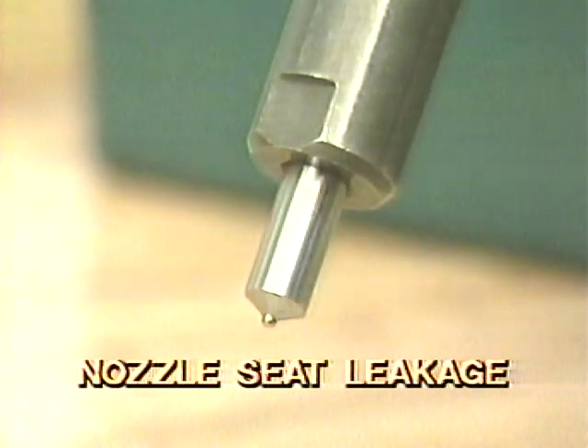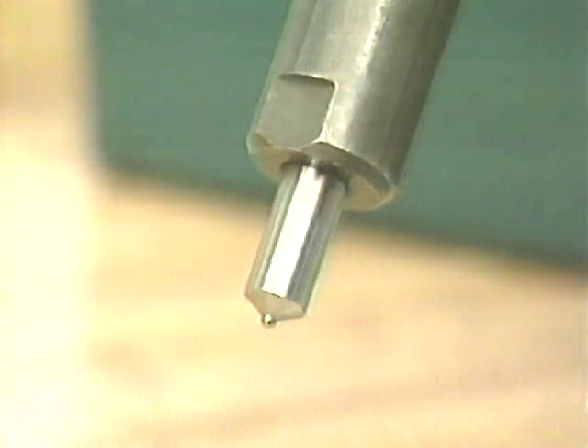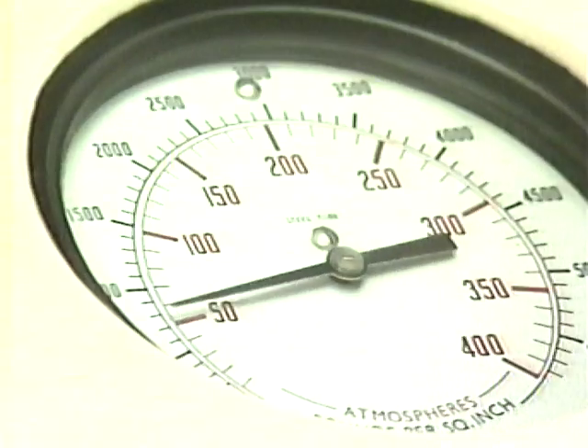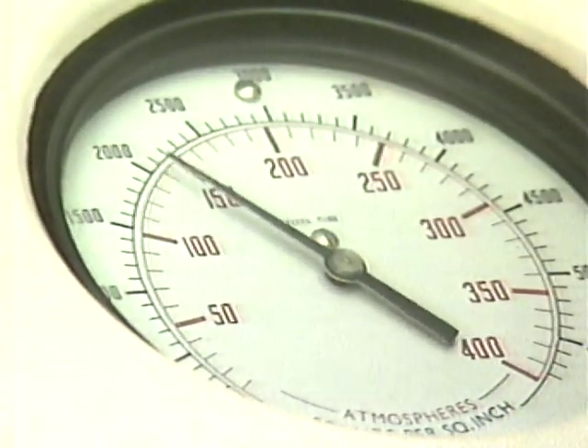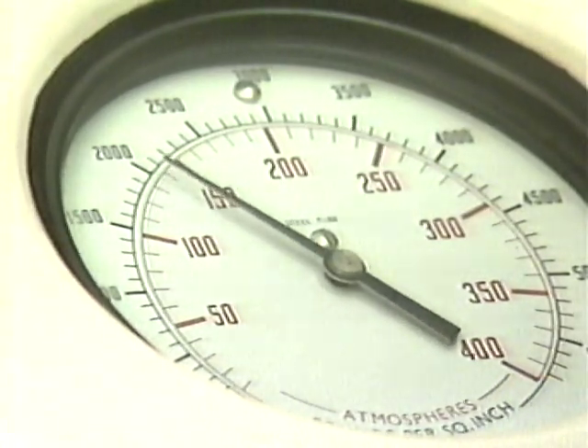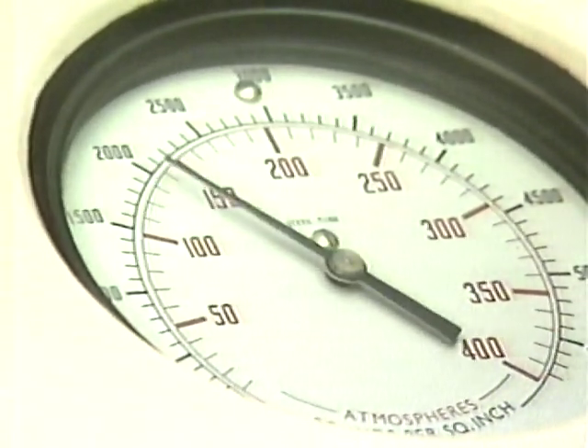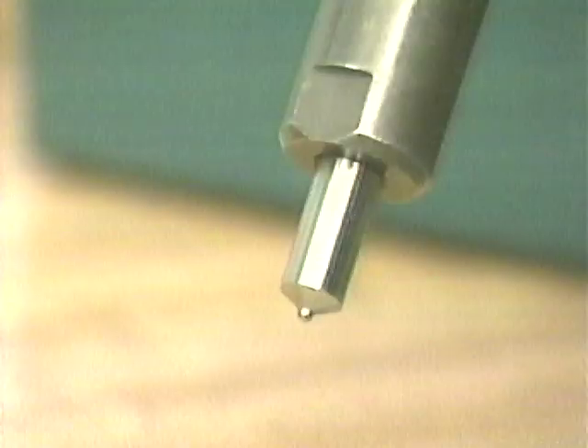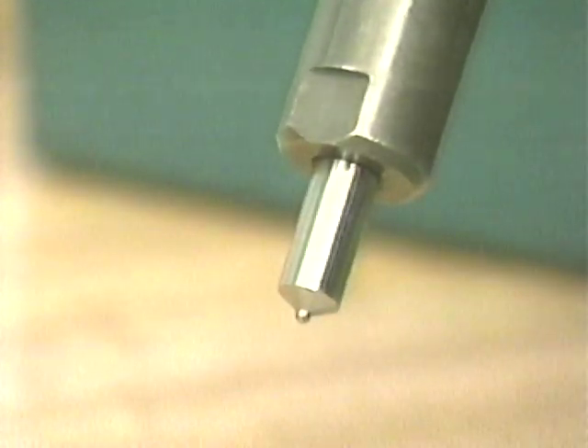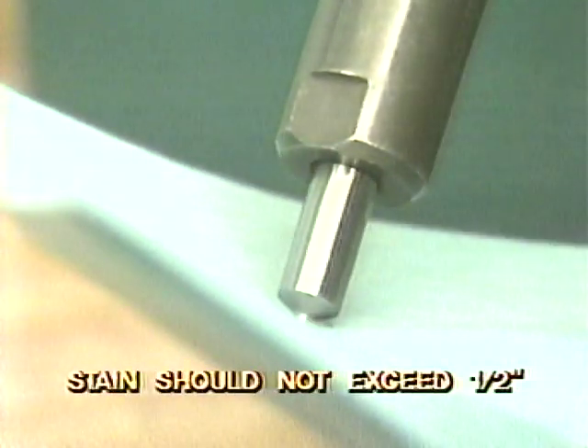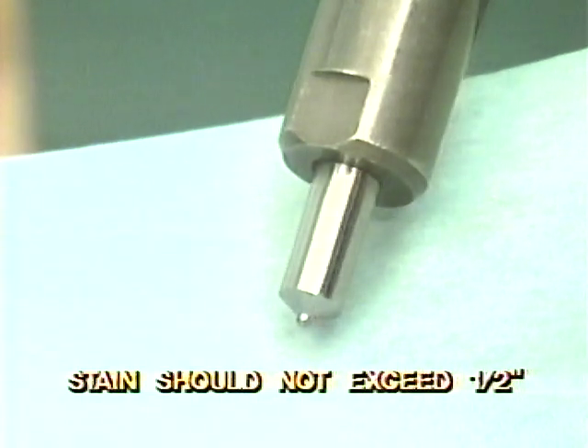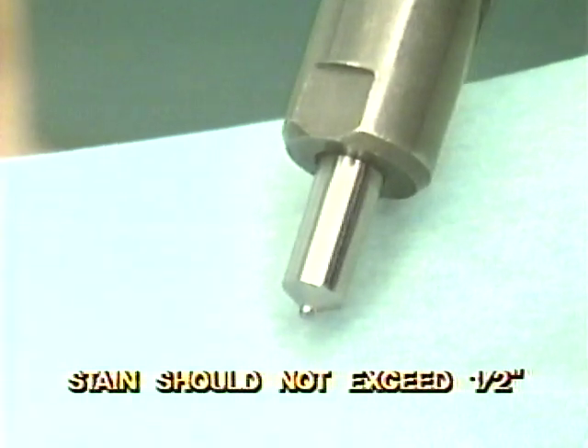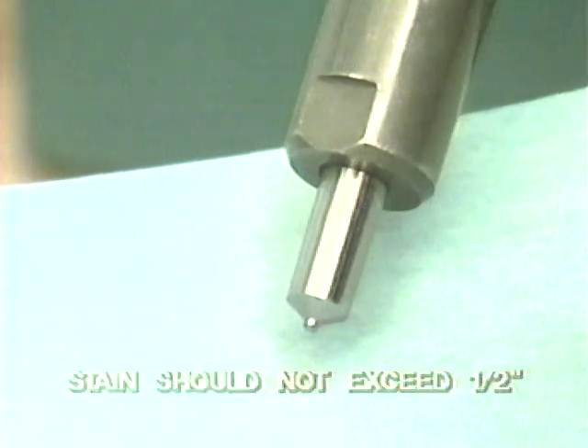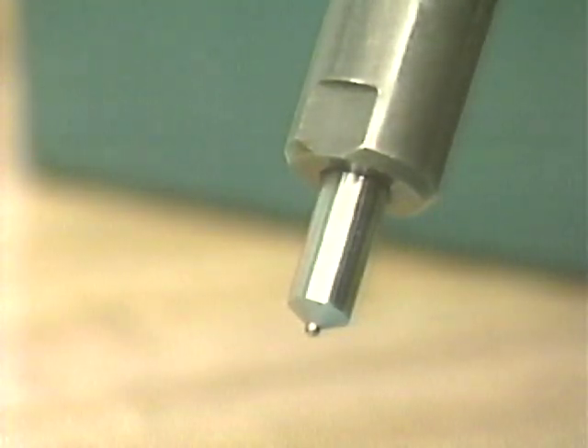The next test is the check for nozzle seat leakage. Wipe the nozzle tip dry with clean blotting paper. Apply a pressure equal to 150 pounds per square inch less than the nozzle opening pressure. Hold this pressure for 10 seconds. Apply a piece of blotting paper to the tip of the nozzle. The resulting oil stain should not exceed a diameter of 1/2 inch. If the leakage exceeds this, the nozzle will require servicing.